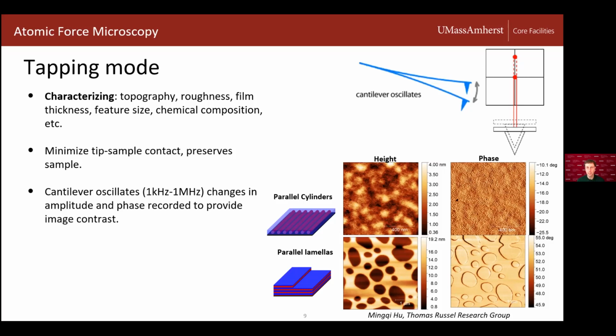Because we have an oscillating probe, we also have the ability to monitor something called phase, which is whether or not the oscillating cantilever's frequency is changing, right? And so we could see some change in this oscillation as a result of any sort of chemical interactions between the probe and the sample, as well as any other interactive, repulsive, or attractive forces.